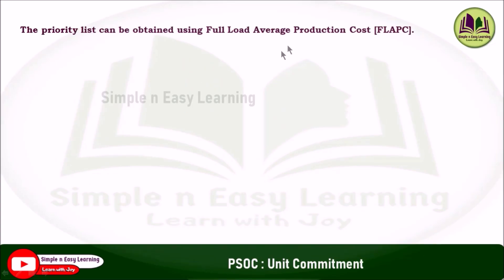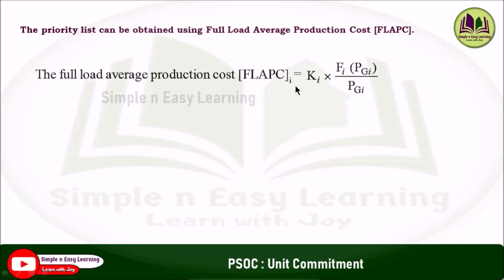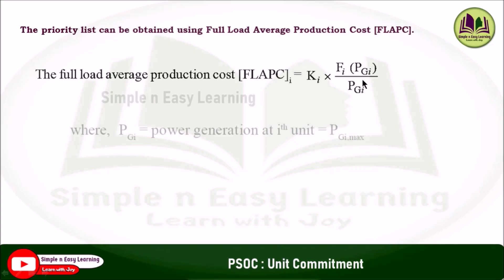The priority list can be obtained using full load average production cost. The formula FLAPC_i is equal to K_i multiplied by F_i(PG_i) divided by PG_i, where K_i is the fuel cost and F_i(PG_i) is the fuel cost function evaluated at PG_i max — the maximum power generation of the i-th unit. From the generation limits, select the maximum value to substitute into the fuel cost function in the numerator, and substitute PG_i max in the denominator.